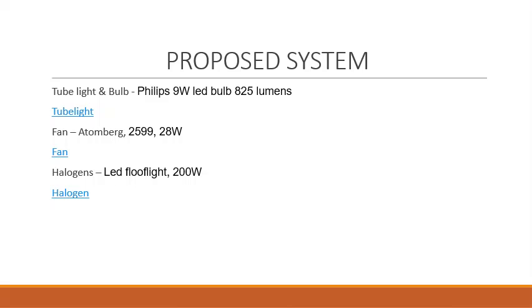The changes that we have made: the tube lights and bulbs that were given in the initial system, we are going to replace both of them by a Philips 9 watt LED bulb that is giving out 825 lumens, which is in the range of the initial tube lights and bulbs. So it won't be reducing the intensity, but it will just be reducing the power requirement for the light. The change in the fan is that we are installing a new fan that is Atomberg, and its power requirement is 28 watts, and it is also operated by a remote control.